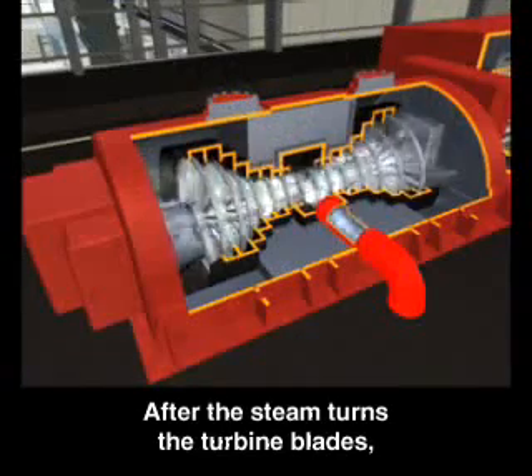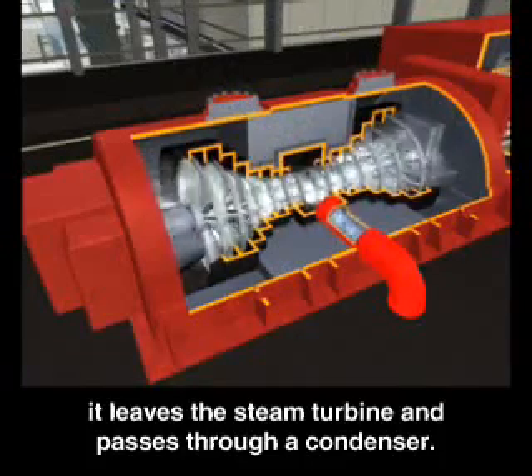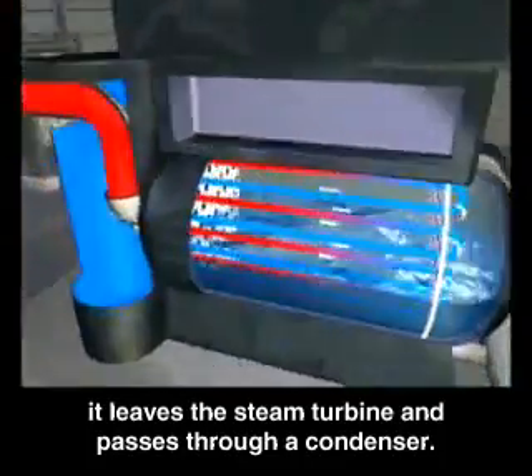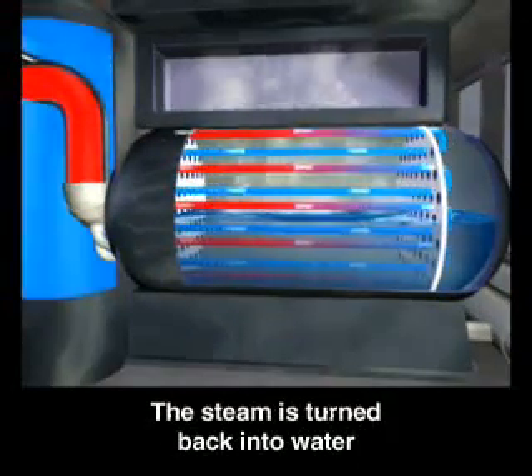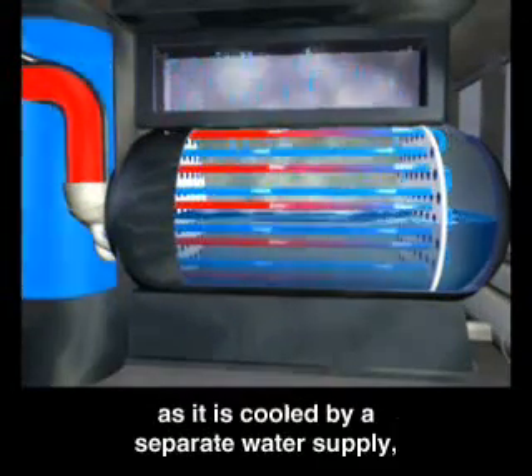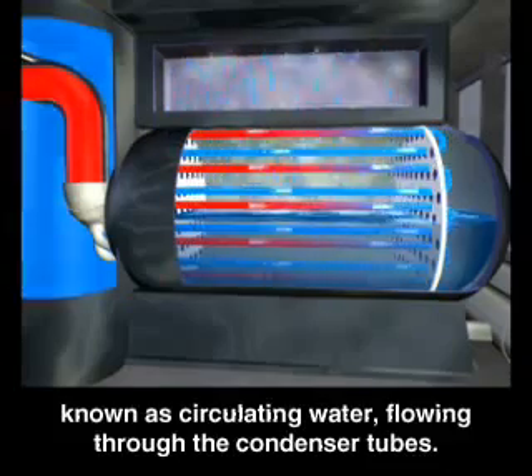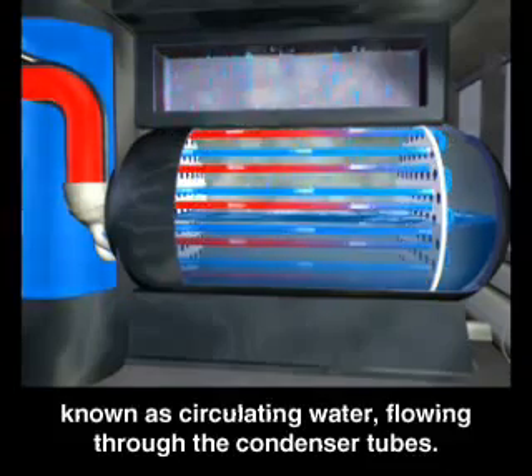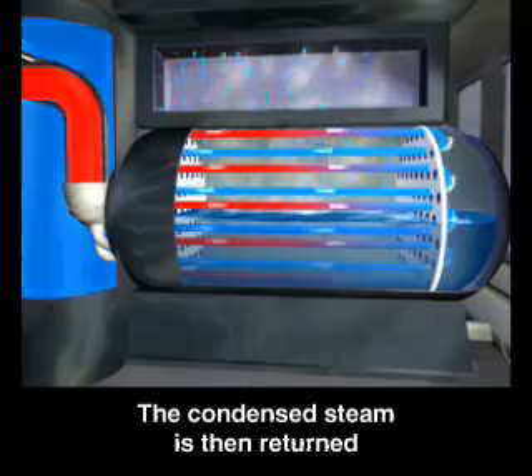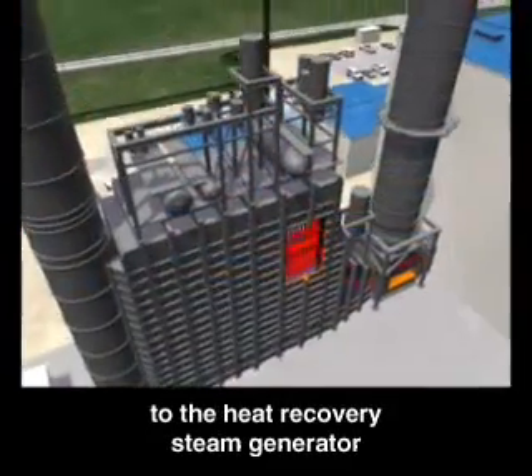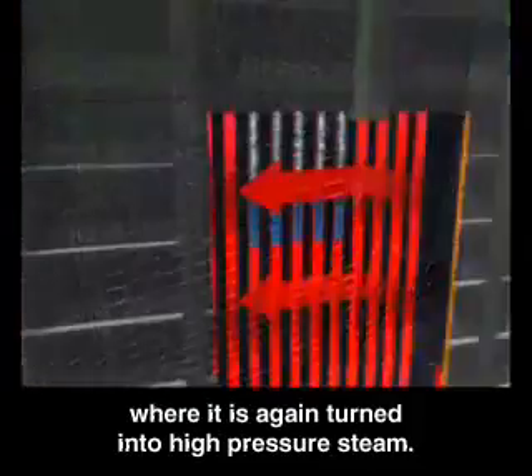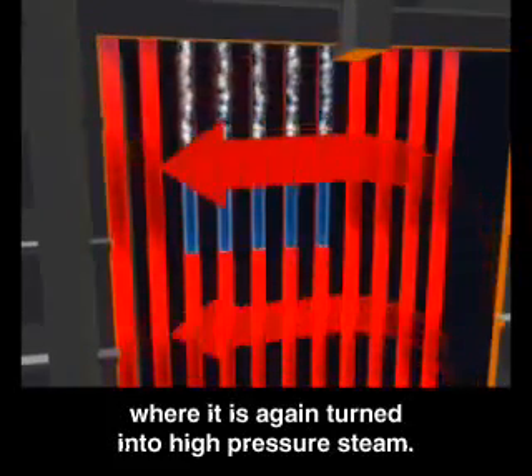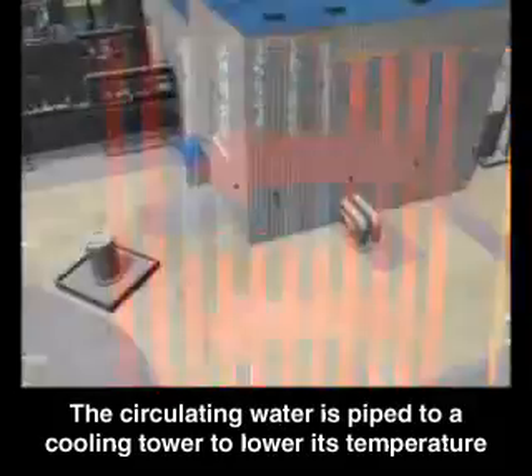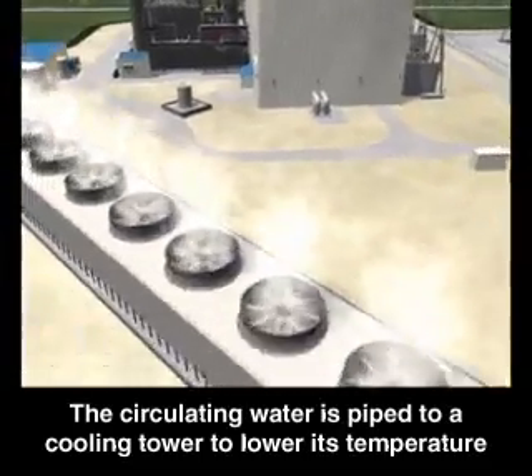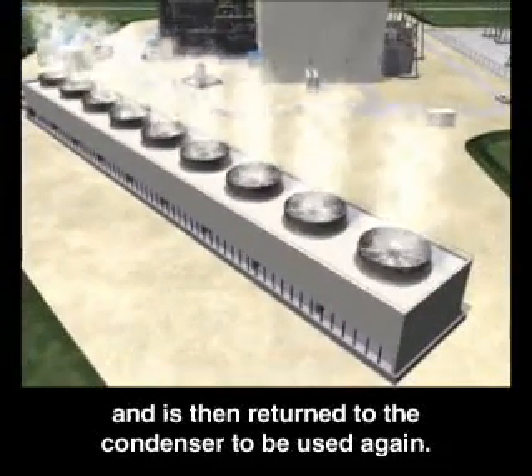After the steam turns the turbine blades, it leaves the steam turbine and passes through a condenser. The steam is turned back into water as it is cooled by a separate water supply, known as circulating water, flowing through the condenser tubes. The condensed steam is then returned to the heat recovery steam generator, where it is again turned into high-pressure steam. The circulating water is piped to a cooling tower to lower its temperature and is then returned to the condenser to be used again.